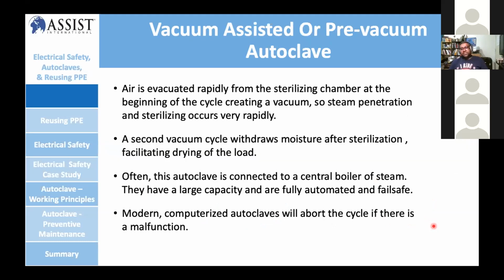When you talk about vacuum assist or pre-vacuum autoclave, air is evacuated rapidly from the sterilizer chamber at the beginning of the cycle, creating a vacuum. So the steam penetrates and sterilization occurs very rapidly. So removing air and creating a vacuum in the chamber, the steam ascends to penetrate and sterilize. A second vacuum cycle withdraws the moisture after the sterilization process and facilitates drying of the load. So the purpose of the second vacuum is to make sure to remove the moisture.